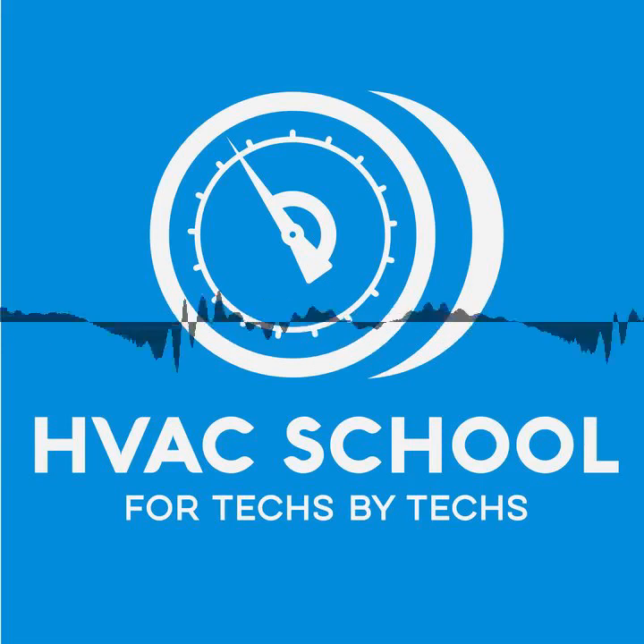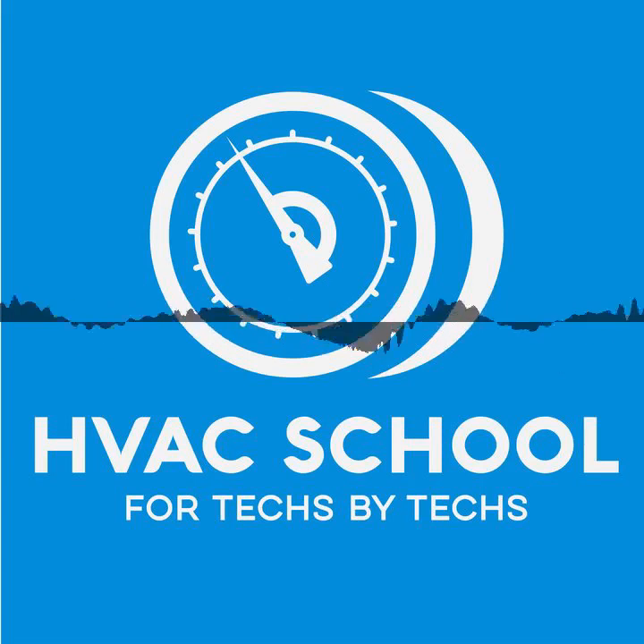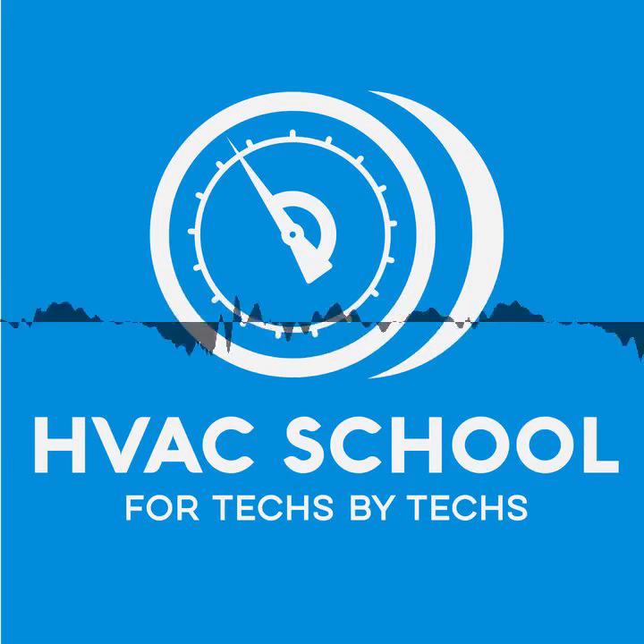And it's also just a great way to get your indoor wet bulb and dry bulb, which you need anyway if you're going to calculate superheat on a fixed orifice system. If you want to use it to calculate target delta T, air temperature split, it's also great for that. It's just a good all-around temperature measurement device. Plus, it gives you that additional data that you can only get from a thermohygrometer, and you have the ability to get it in the duct.